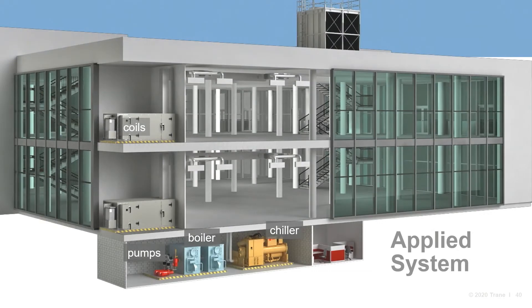When we talk about applied systems, we assume that the system contains a centralized chilled water generator, typically a chiller, and a centralized hot water generator, typically a gas-fired boiler. Pumps move the water from the centralized plant through a network of pipes to the terminal units, often coils. The coils then transfer their energy to the space being conditioned, and the water enters the return line and is pumped back to the central plant.